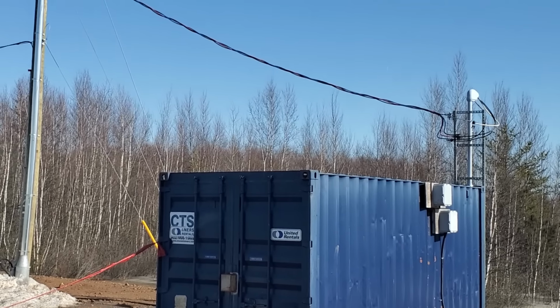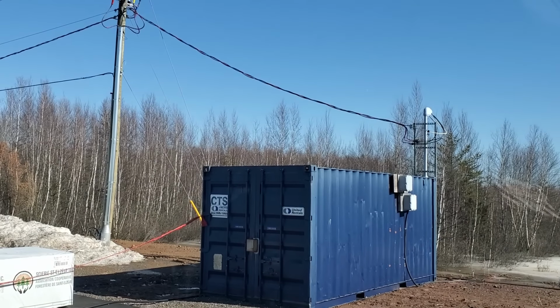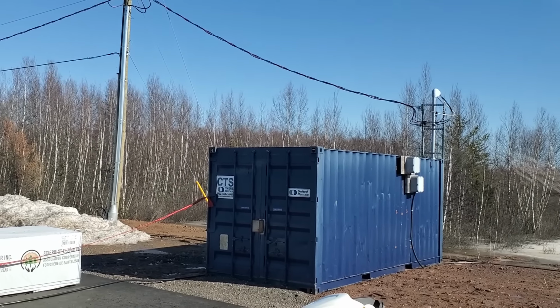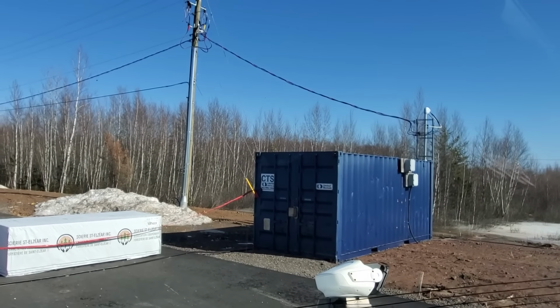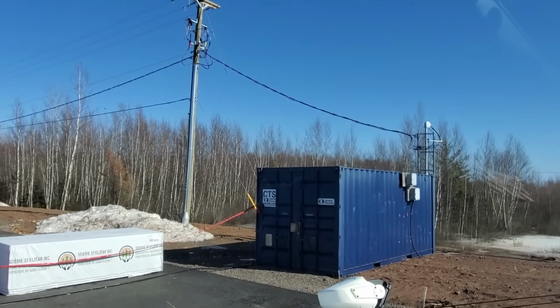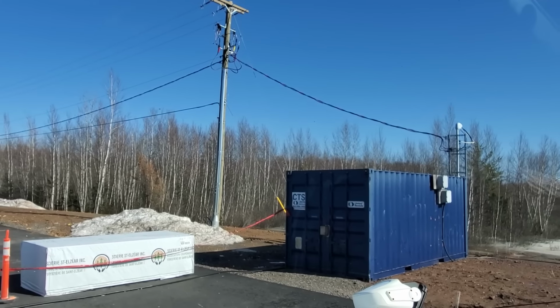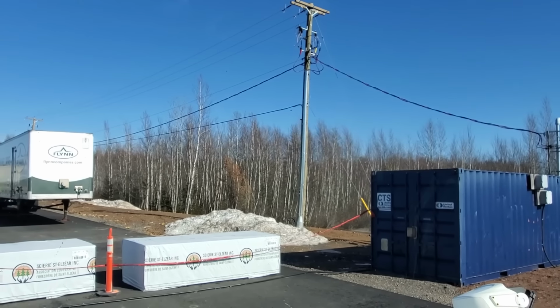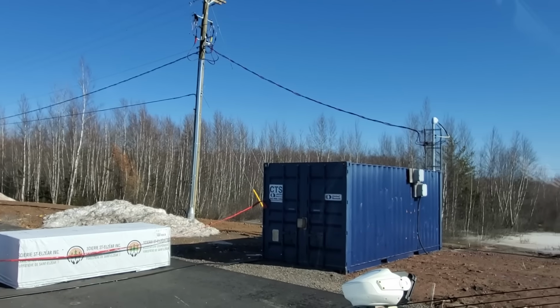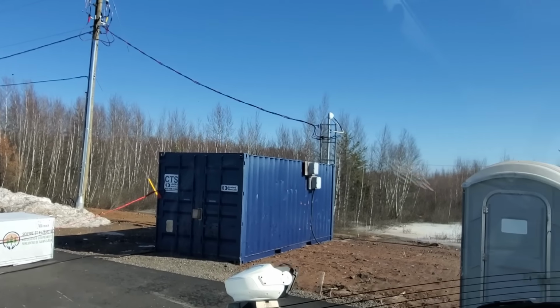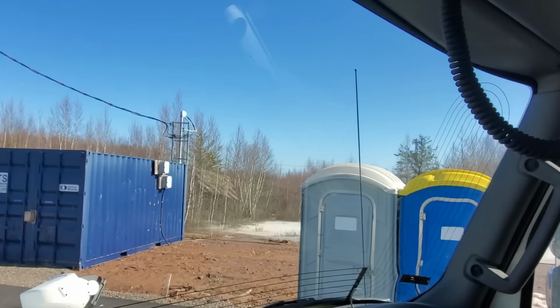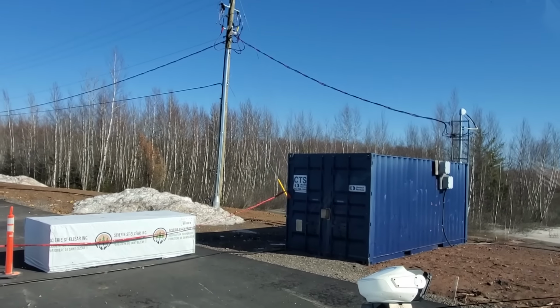Some quadruplex run, some 3-phase low voltage cable going over to this C-can feeding temporary power. So we're not allowed to have 2 feeds going into a building. I'm not sure if they have that teck cable running into the main meter room, what the story is there. So we're definitely going to be looking at that. We may end up disconnecting that before energizing it. There could be, of course, another cable running to a construction trailer over here behind me.